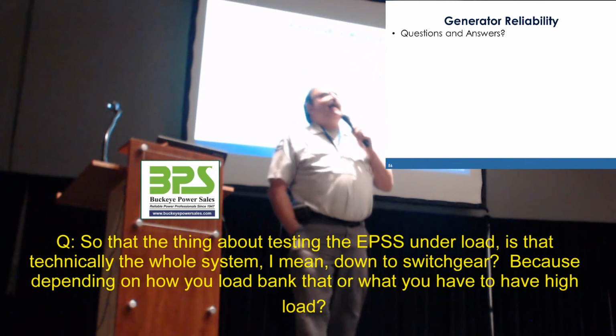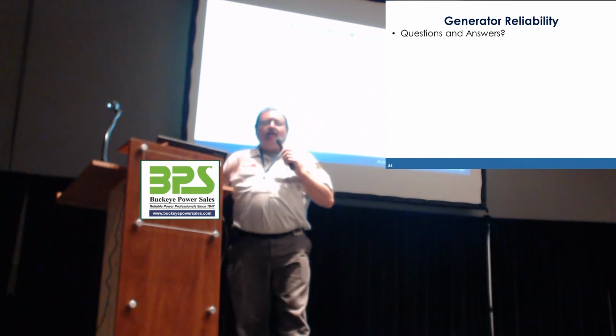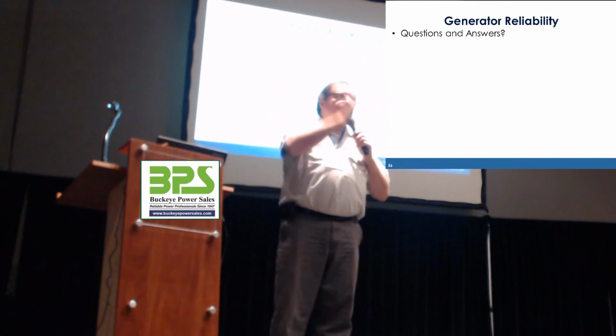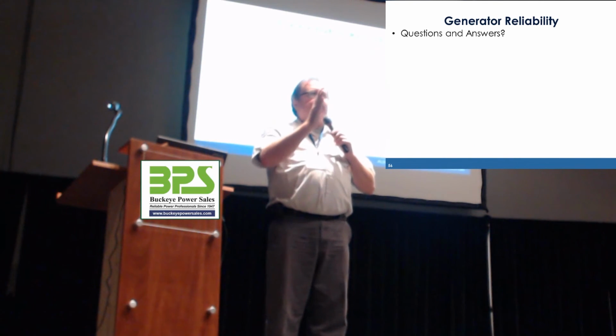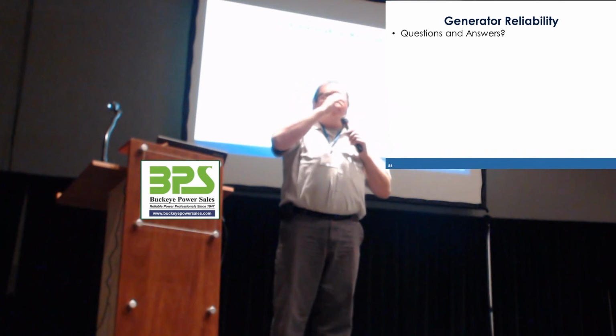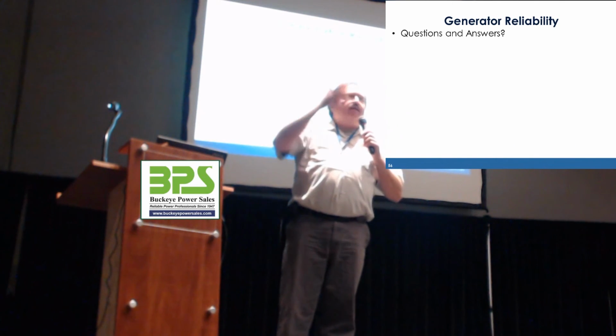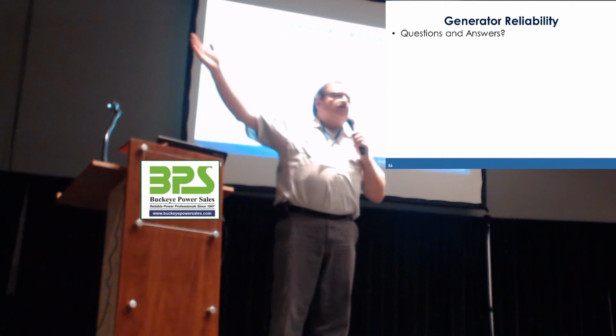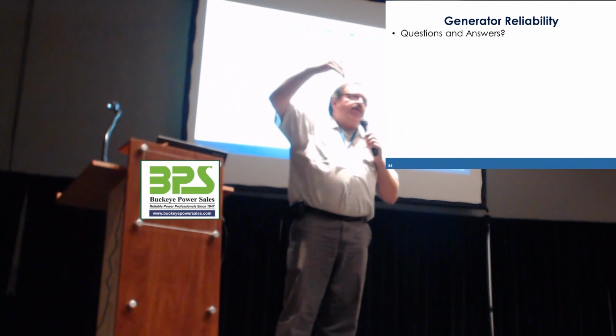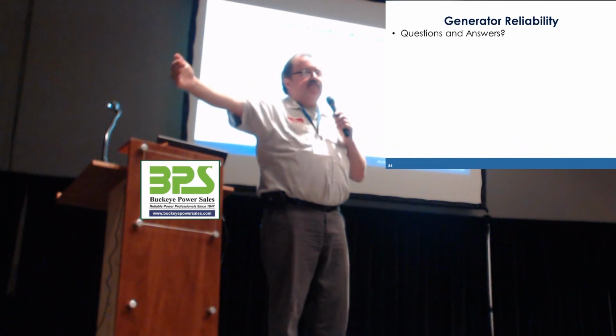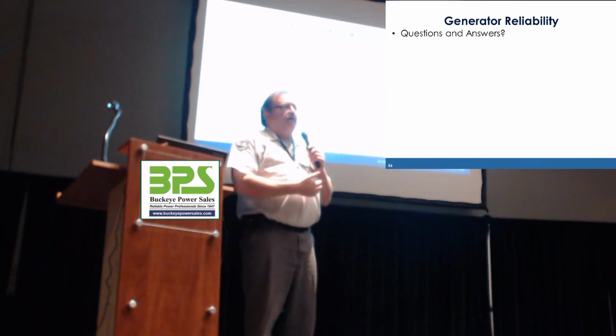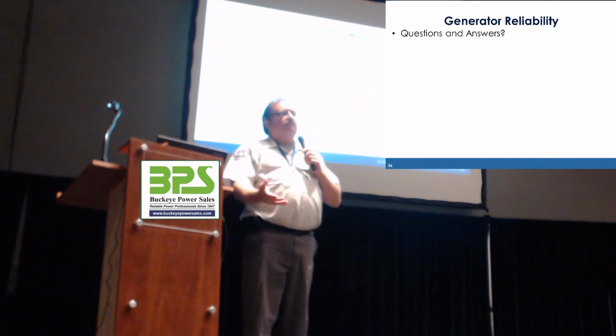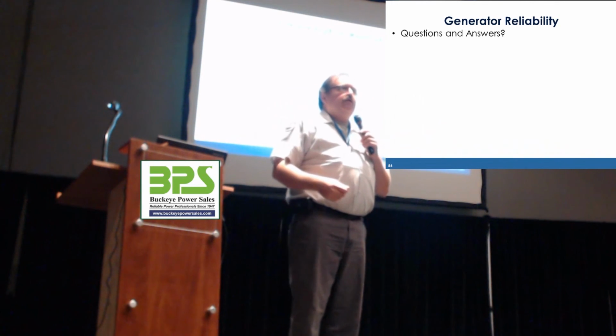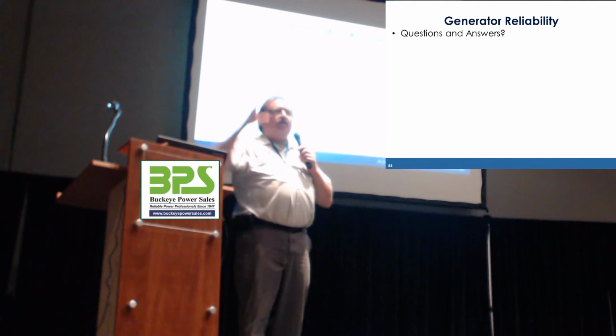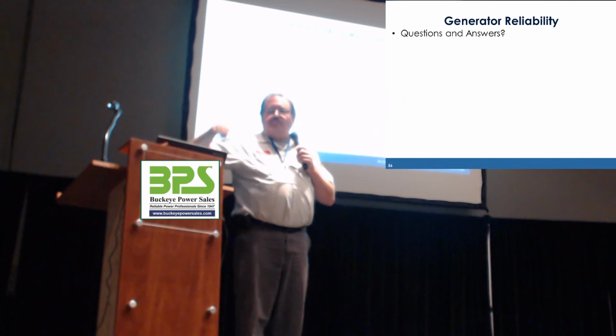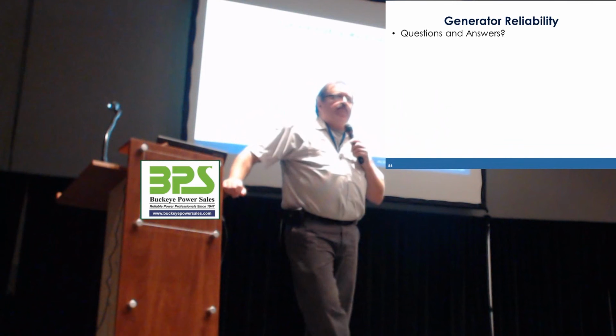It does not have to be, well, in a healthcare setting, the transfer switch itself has to transfer. Now, if that transfer switch, or if it's paralleling gear, is still going to be feeding your load, right? Even if there's a utility coming in, you're still having to feed a live load. Now, you can supplement in that paralleling gear. You can have a breaker set up for a load bank that you could supplement that load. But the gear itself, or the transfer mechanism, by NFPA 110 still has to transfer monthly.